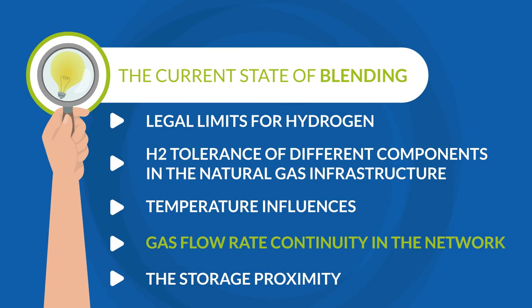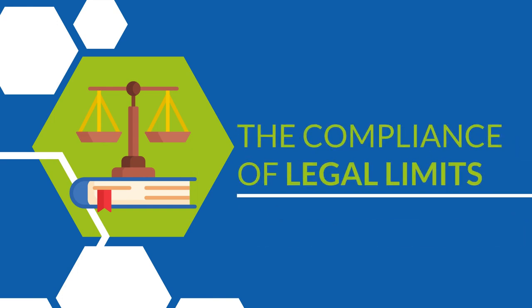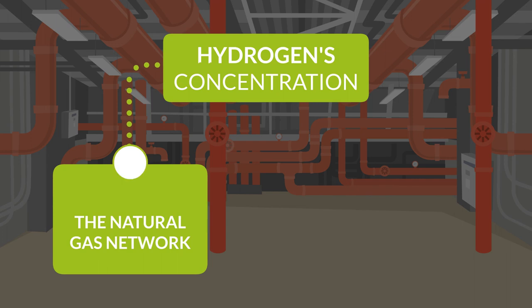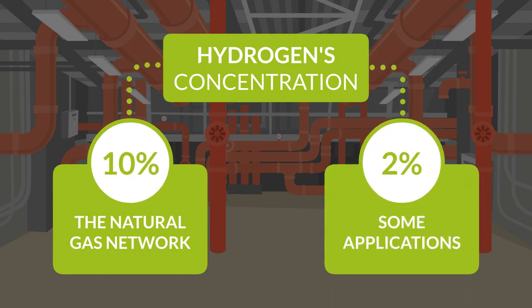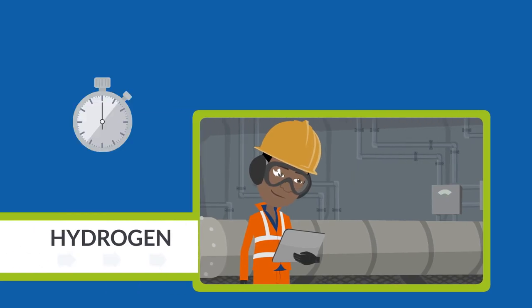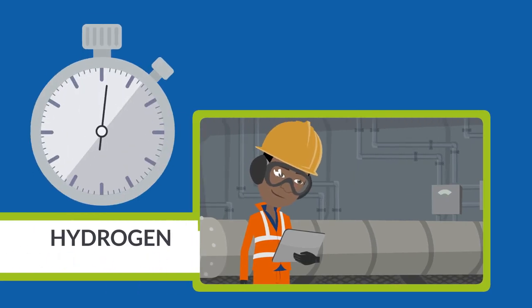The natural gas flow in the grid is another aspect to watch when blending hydrogen. The significance lies in the impact it can have on the compliance of legal limits. Since hydrogen's concentration in the natural gas network is about 10%, and for some applications it can't be above 2%, monitoring gas flow rate is essential to decide when and where to feed H2 into the grid.